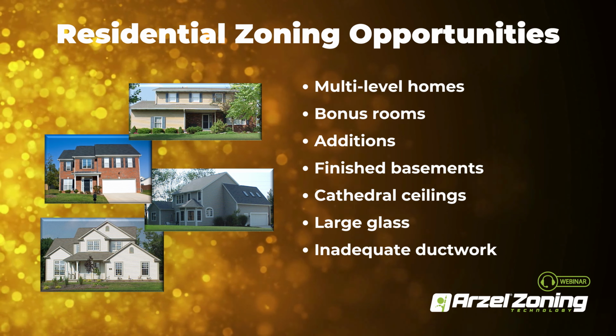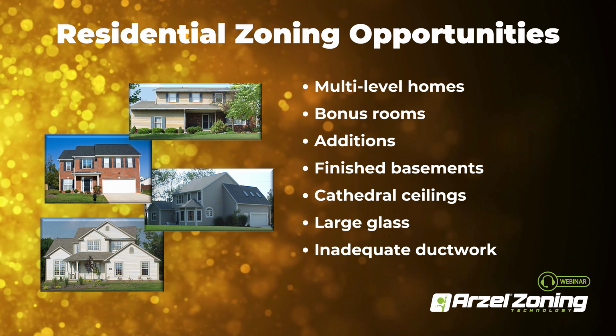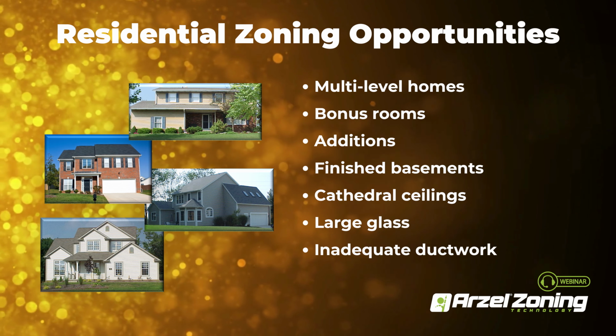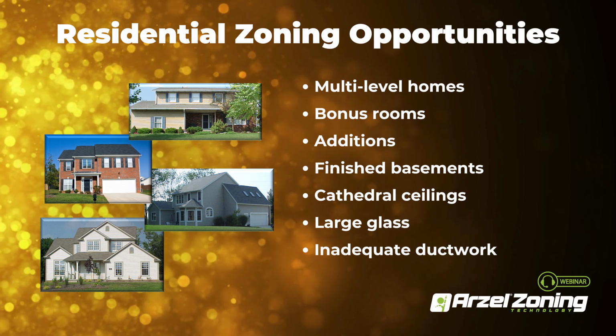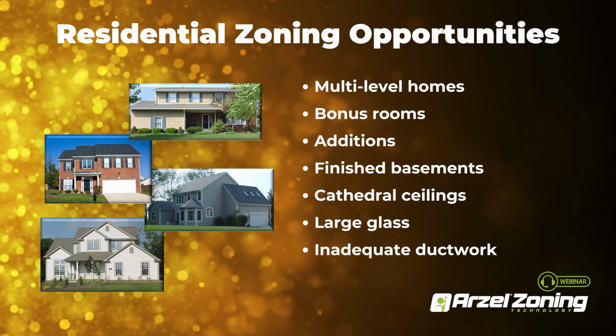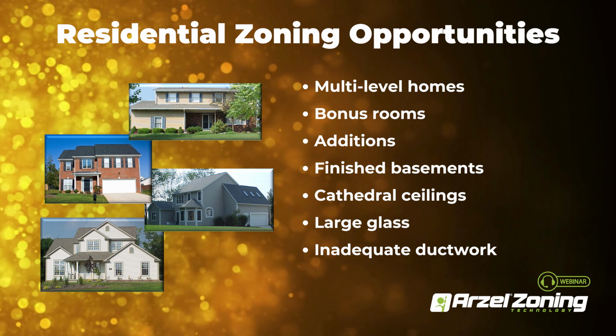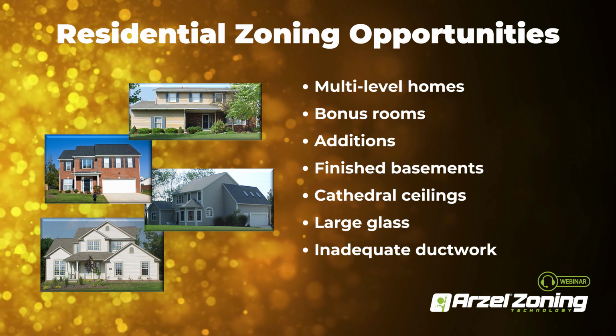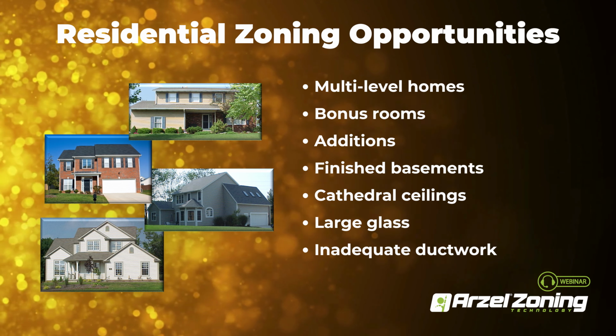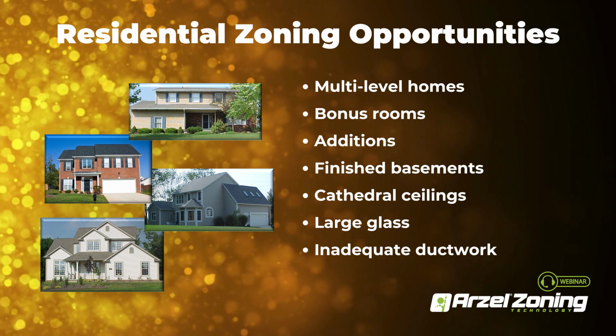If we improve the velocity from our registers, zoning will help with that. But if we don't have adequate ductwork there, maybe they've got one of those Cape Cod colonials that has the lofted area, and they've only got 1 or 2 6-inch runs feeding a 600-700 square foot area. Zoning's not a solution for that. You have to be able to get the ductwork up there to take care of it.